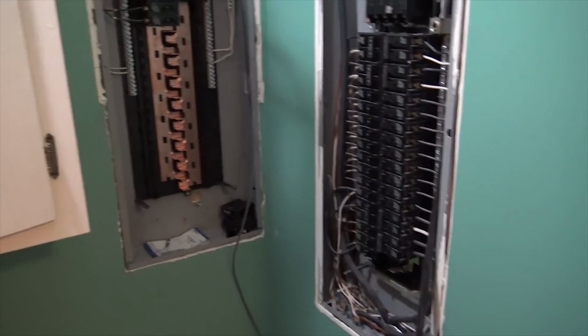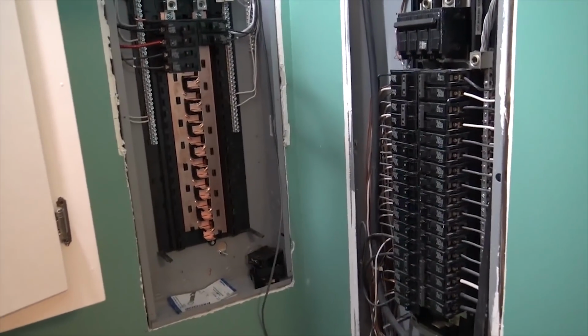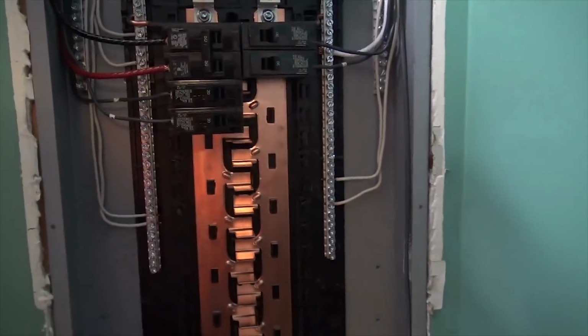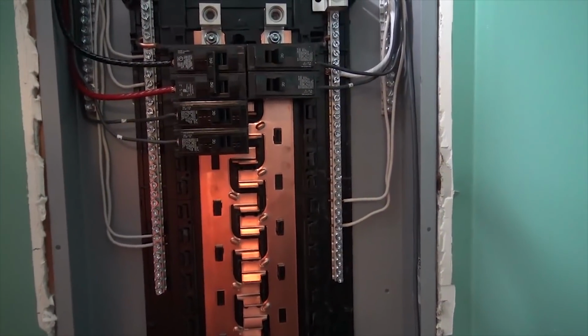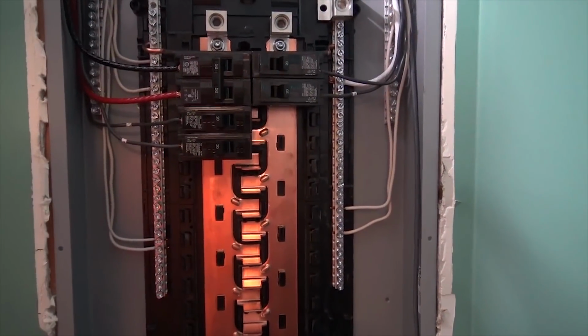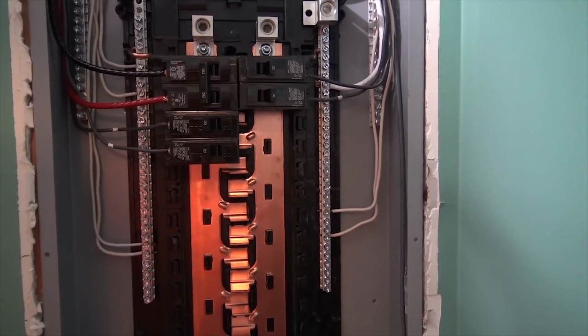And so we got a lot of work to do. It's the end of day 4, but we're getting it. This project will have 3 critical loads panels fed by the inverter. He has a propane furnace. We're going to put in a circuit in here that will allow the furnace to run in a grid down, because it only needs a blower, and because he's got propane.